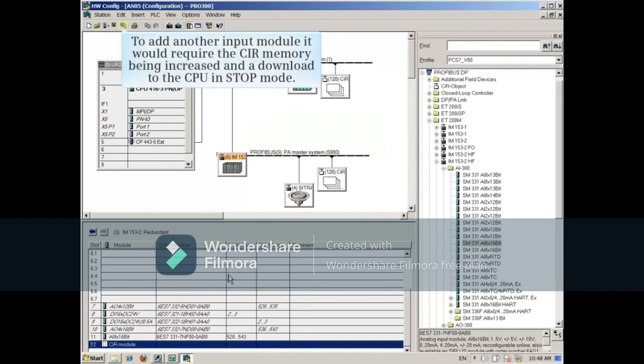If I have to add another input module, it would require the CIR memory being increased and a download to the CPU in stop mode.